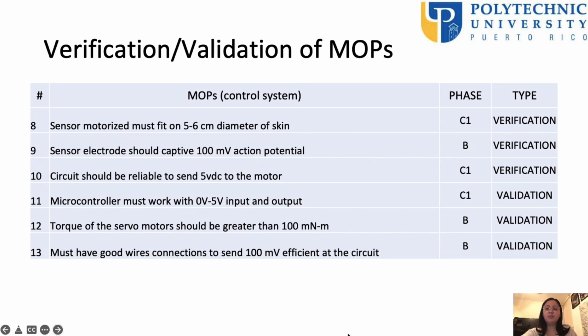Verification and validation of MOPs for the control system: the sensor motor must fit a 5 to 6 centimeter diameter of skin (verification); sensor electrode should capture 100 millivolts action potential (verification); circuit should reliably send 5 volts to the motor (verification); microcontroller must work with 0 to 5 volt input and output (validation); torque of the servo motors should be greater than 100 (validation); and it must have good wire connectors to send 100 millivolts efficiently to the circuit (validation).